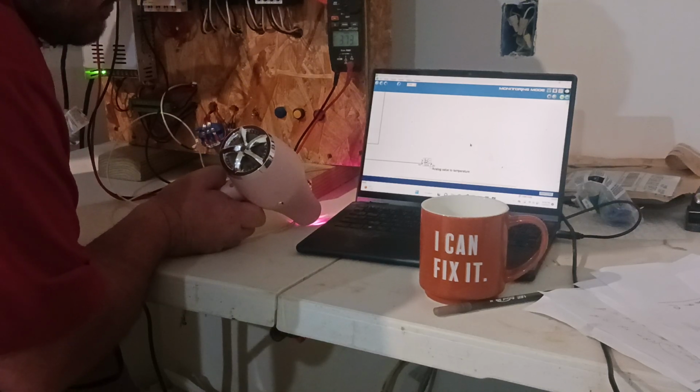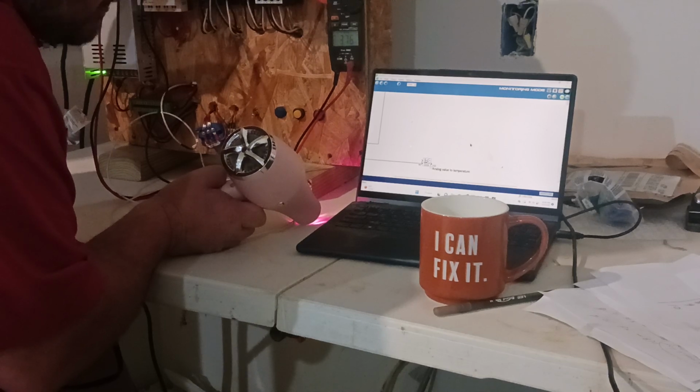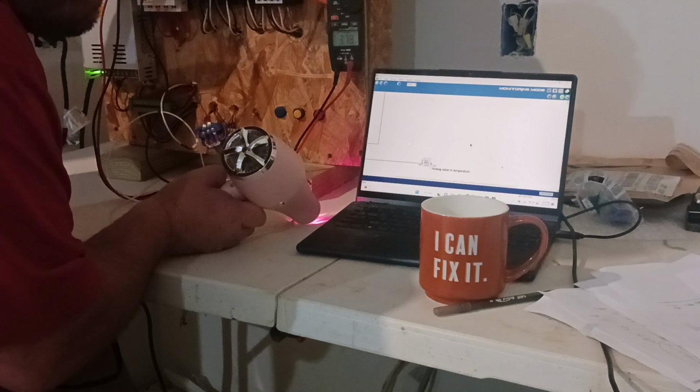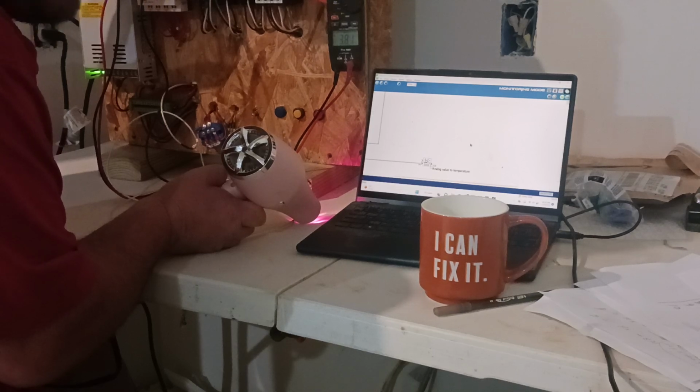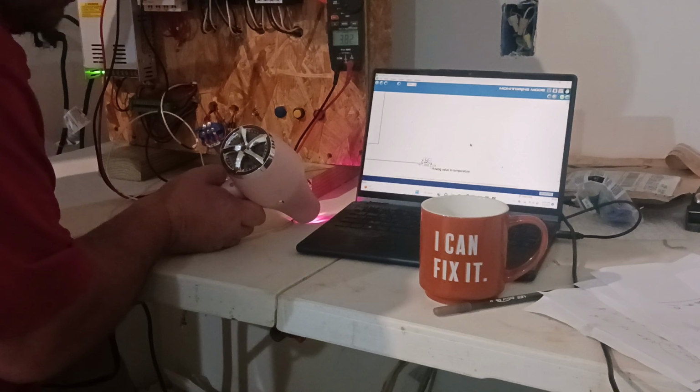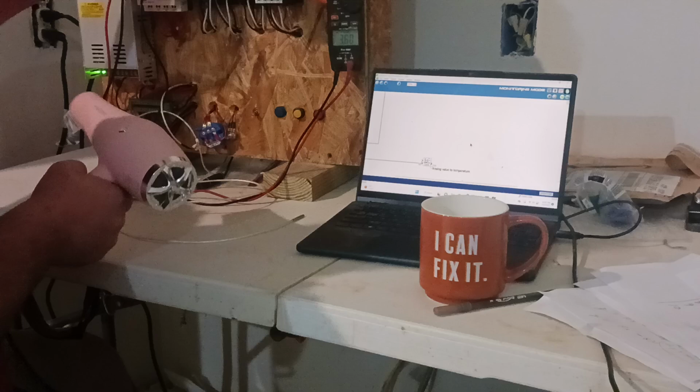See, my temperature's up to 90 and my voltage is 3.74. Temperature's up to 102 and my voltage is 3.78, 3.79, 3.8. See how my voltage on my meter is increasing as my temperature down there increases. I'm at 114, and that's good enough.